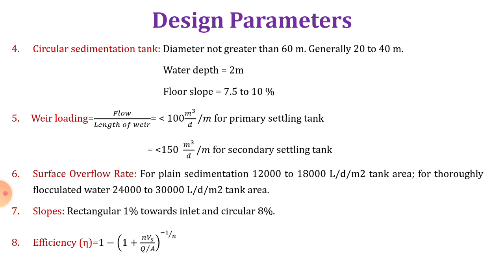Surface overflow rate for plain sedimentation should be between 12,000 to 18,000 liters per day per meter square of tank area. For thoroughly flocculated water it should be between 24,000 to 30,000 liters per day per meter square of tank area. Slope for rectangular tanks is 1 percent toward the inlet and for circular it is 8 percent. The efficiency eta is given by: 1 − (1 + N·Vs / (Q/A))^(−1/N).